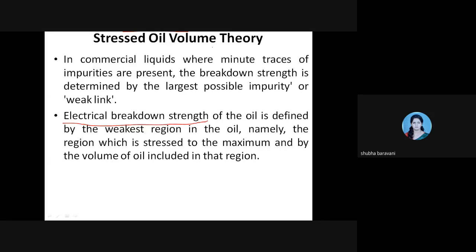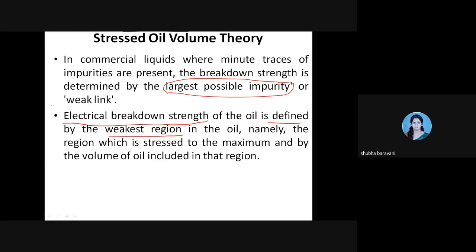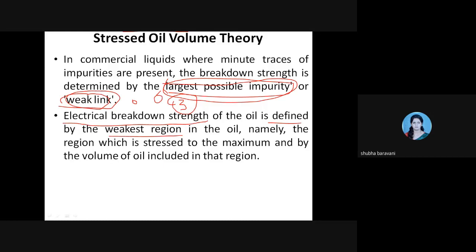In the first statement, the breakdown strength is determined by the largest possible impurity, which has more affinity — it gets charged easily. For example, out of impurity 1, impurity 2, and impurity 3, impurity 3 is the largest and has the most affinity towards electrical charges, forming the weakest link. The second statement says the region of the liquid dielectric where impurity 3 exists is stressed to the maximum compared to other regions.